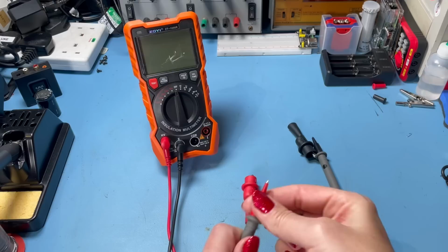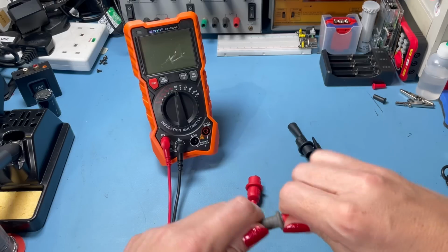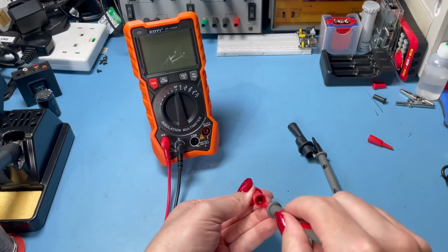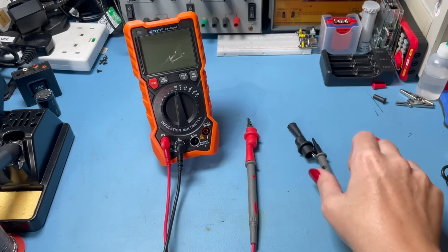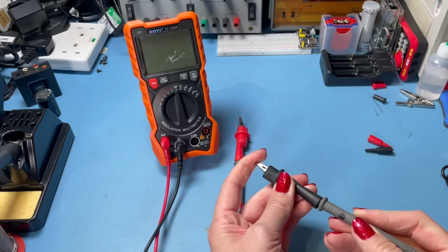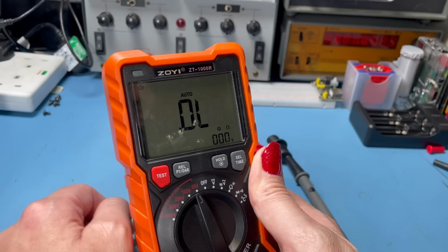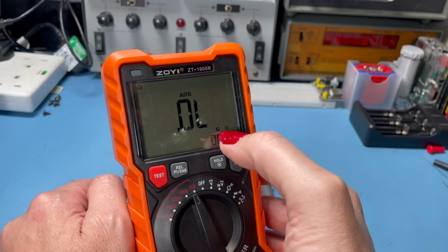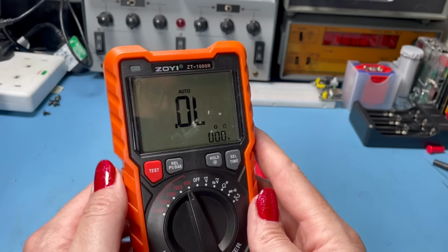That would be bad. I'm going to be wanting to take these guards off here to get these in. Nice. Let's make sure I've got that in there properly. Fantastico. Right. So this will do insulation resistance testing up to 20 gigohms. So you can measure two different parameters with this meter.